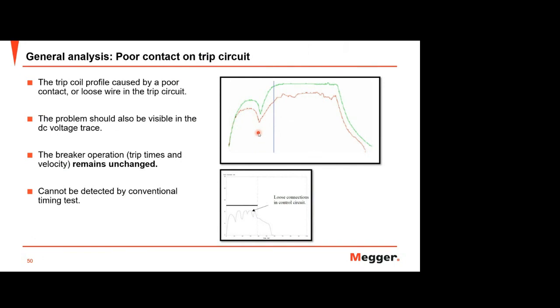So a loose fuse in the breaker cabinet can often cause this type of fault. However, in this case the problem should be visible in the DC voltage trace actually. Then something is very important. The breaker operation, trip time, and velocities remain unchanged. So meaning you cannot see this fault by conventional testing method. So this is why you want the additional advanced tests, to detect this one. Because with conventional testing you cannot detect it, because the time of the coil and also the mechanical part are still the same. You can just see this issue, and then you need to do investigation later on.